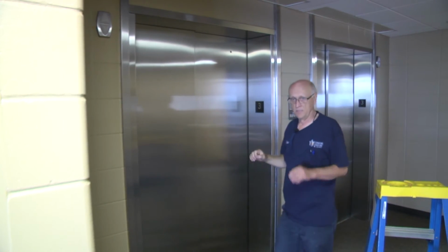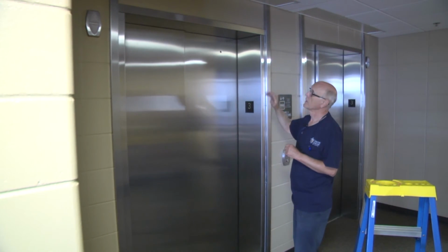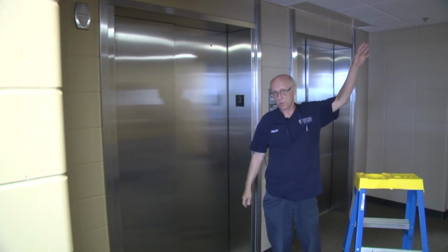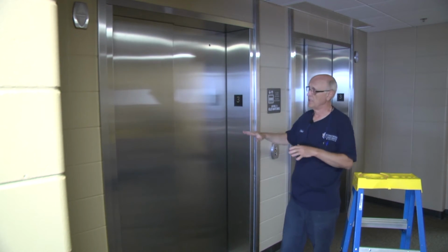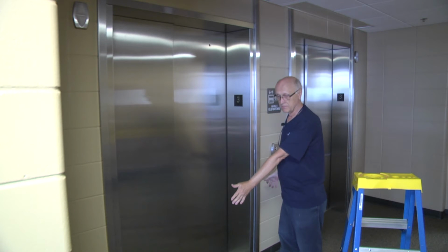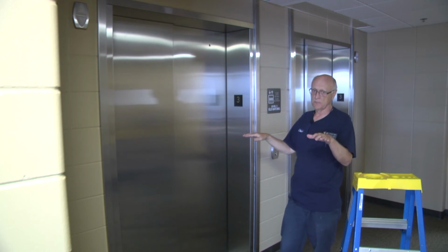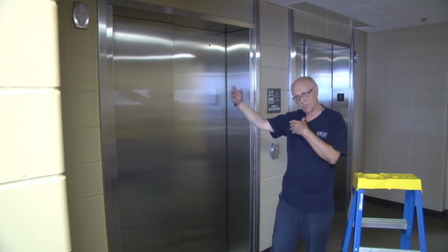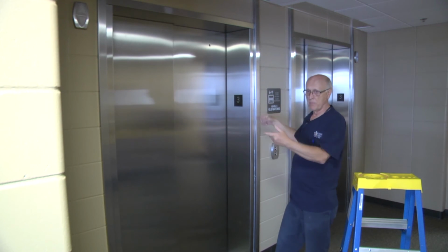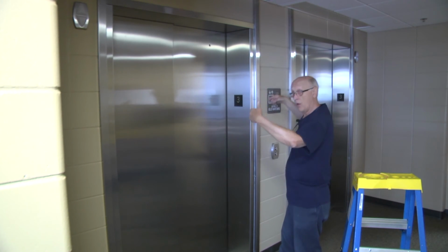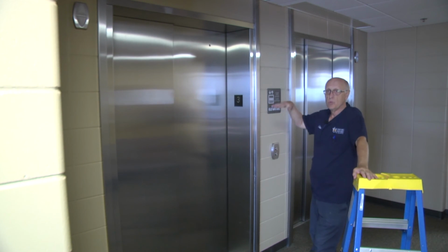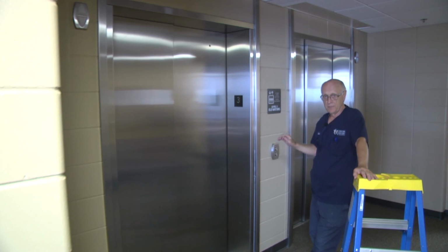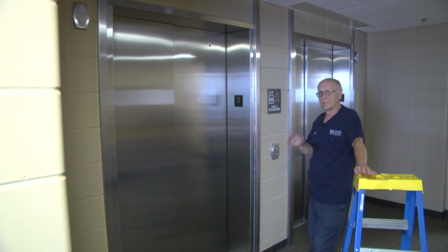So just to review again, they will deploy when either the smoke detector or the sprinkler system goes off in the facility. All floors it comes down to. Once it's over with, to reset it, you're going to reset your fire alarm. It's going to come back online, and they'll all go back up, I hope, all at one time. Again, you will need to go to every floor and check to be sure that they're up. Got any questions? Give me a call.